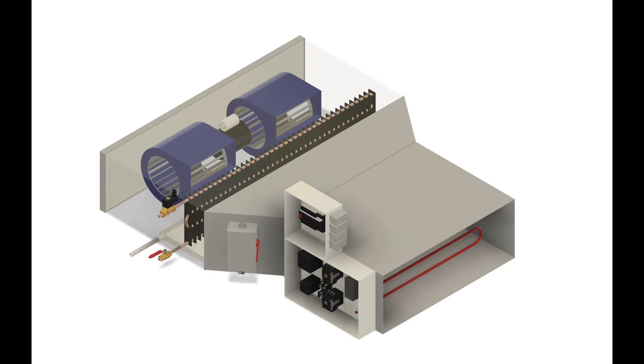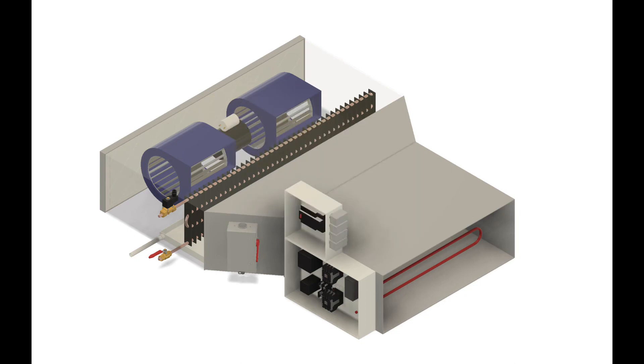Again, if you have a lack of airflow going through your fan coil unit, you want to check to see if your filters are plugged and dirty and need to be replaced. Check to see if the coils need to be cleaned because you need adequate airflow for both heating and cooling mode.